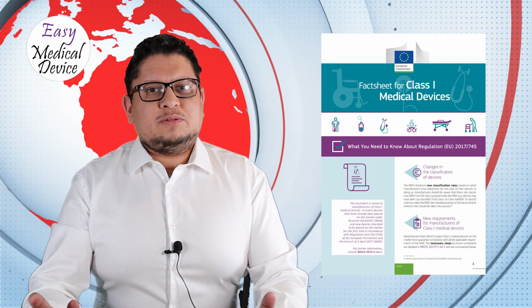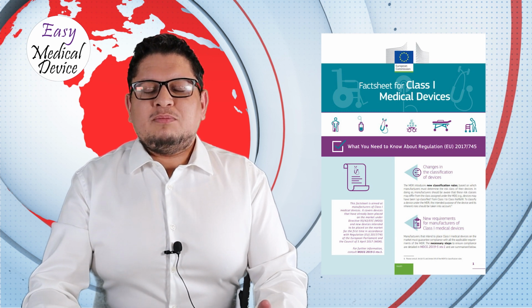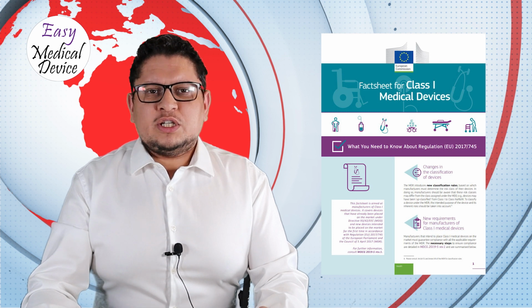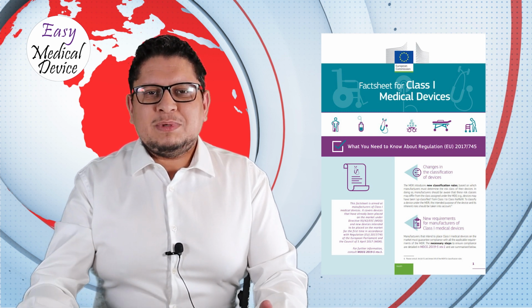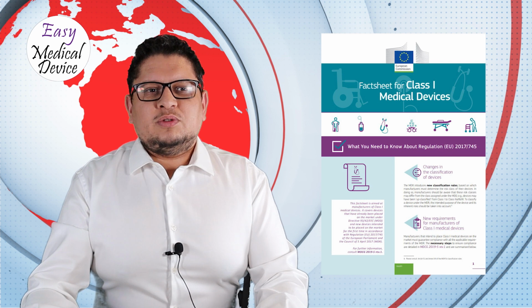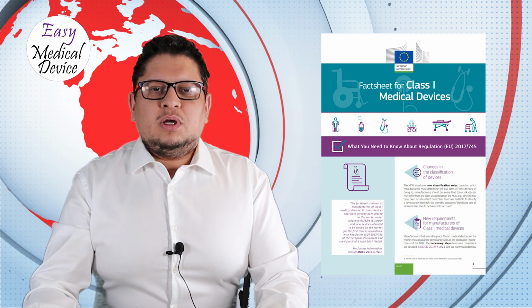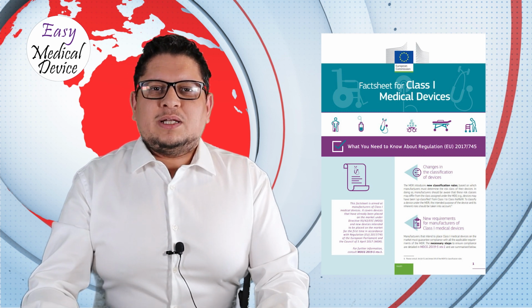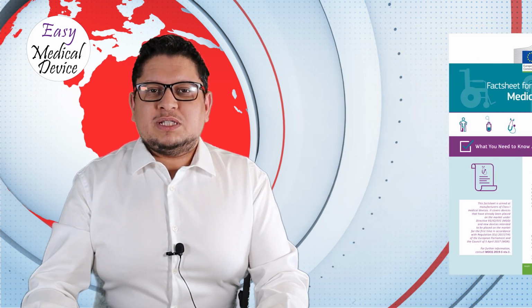The problem is that it's really the last month. So in 1 month, we cannot build the technical file, build the quality management system, build the clinical evaluation, build the risk management file, build all those documents that are needed for your organization. So it's something that can take more time. So anyway, you have to start. Even if you will be late, you have to start so that you will be ready as soon as possible. So mainly this is the point here.